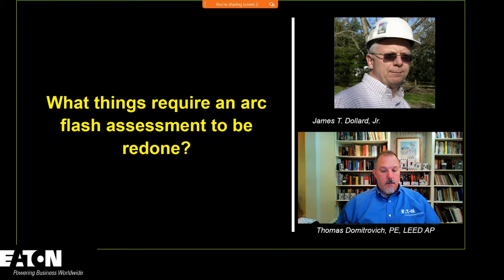the arc flash hazard, but get into Annex K in the 2018 standard and look at some of the updated information there. It tells you that about 98% of fatal occupational electrical injuries are from shock. And there was a study that showed a very large percentage of them, 40%, involved 250 volts or less. What that tells us is indicative of a mindset, and the mindset is that 240 isn't dangerous, 208 isn't dangerous, 120 isn't dangerous. That's a mindset that a wireman has. I know, I am a wireman, I've been there. And they think very differently when they're handling 277 or 480 than 208.